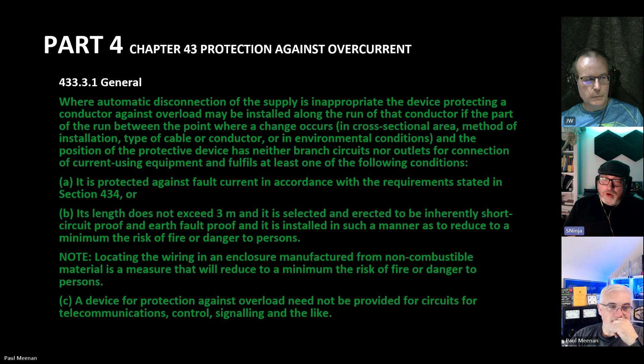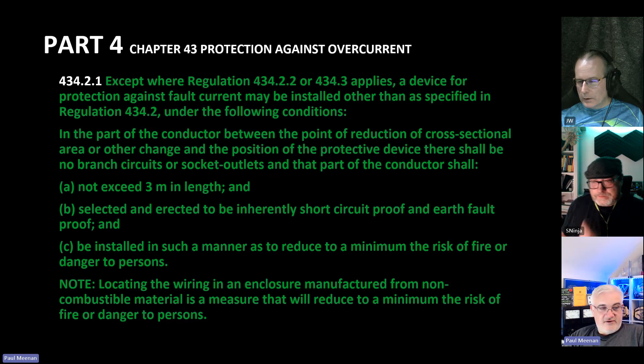434.2.1, except where regulation 434.2.2 or 434.3 applies, a device for protection against fault current may be installed other than as specified in regulation 434. And I think this is very similar to the last one. Basically, it's the exact same thing, but this is fault current, not overcurrent. Yes, overload current. So it talks about not exceeding 3 meters in length, inherently short circuit proof, minimum risk of fire, and in a non-combustible enclosure.